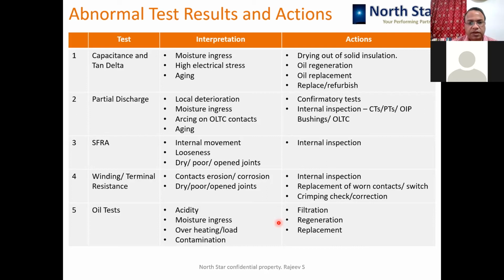Okay. So if winding or terminal resistance is increasing, contact erosion, corrosion is happening, that is a direct indication. And again, there could be a poor joint because of various reasons. So it calls again for the internal inspection, replacement of worn out contacts or switch, and crimping joints, which so many times get opened. So crimping joints are to be checked and corrected accordingly.